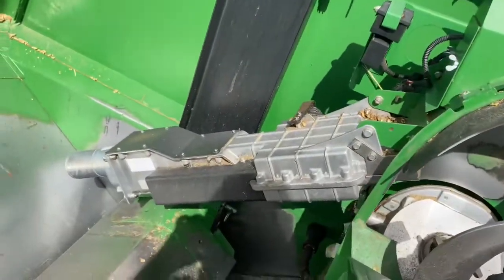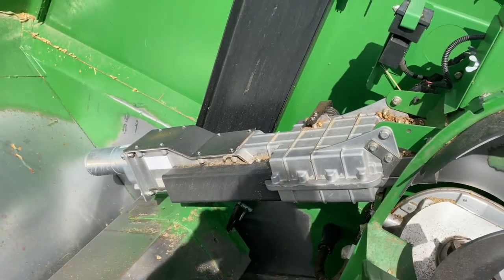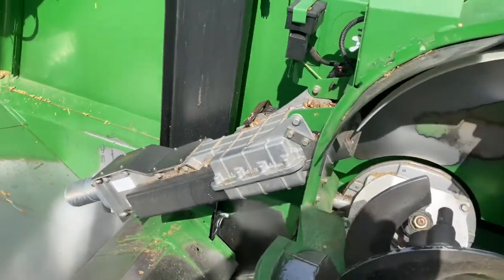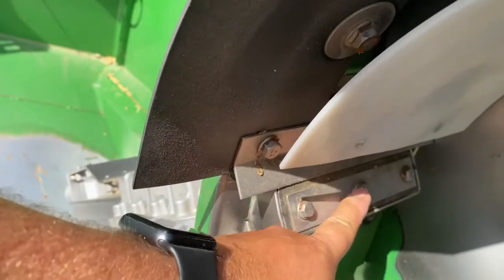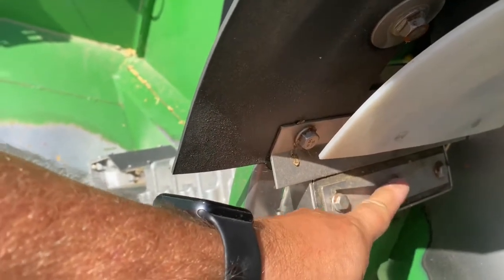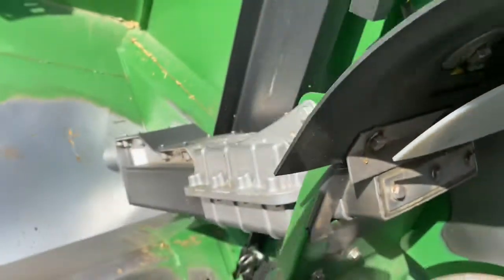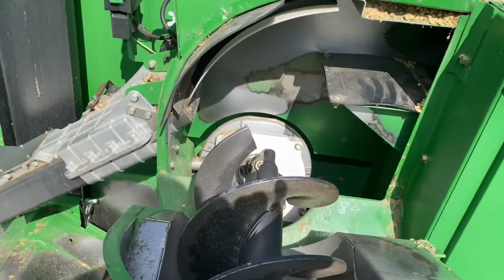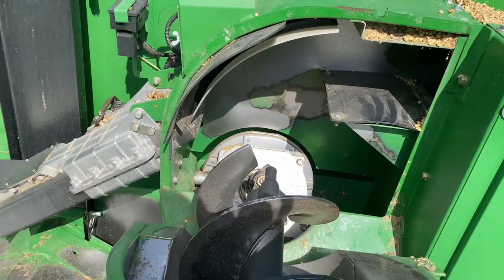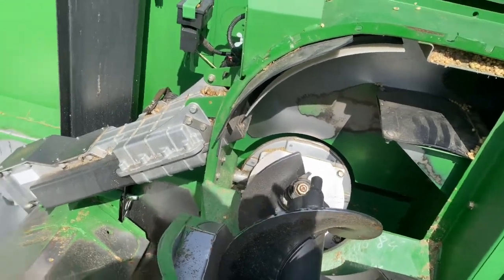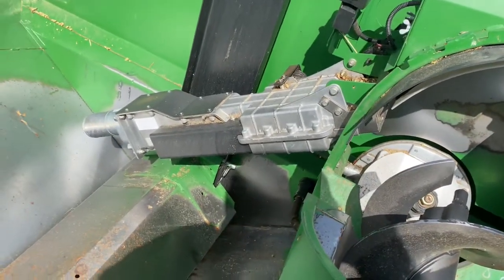As far as moisture sensor maintenance, right here is your plunger, and the center bolt holds the plunger in, so you could take it off and pry it out and look at the capacitance plates inside of it and the plastic around them to make sure they're not worn. You need to be careful with this sensor.